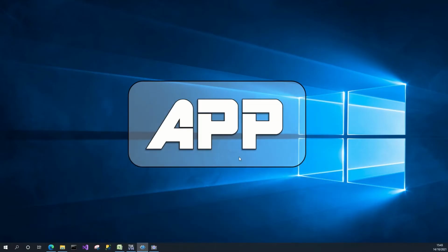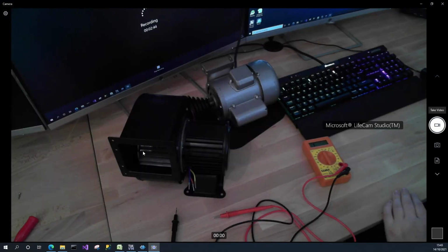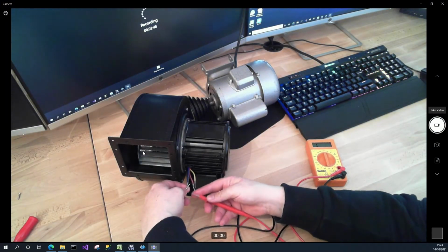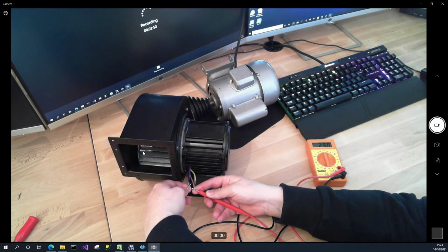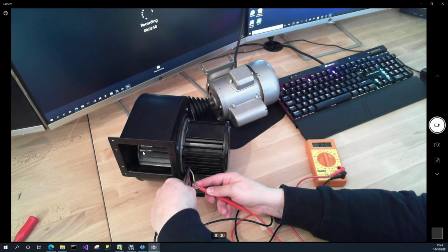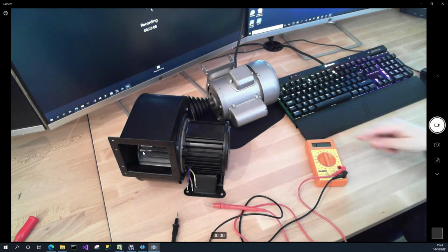So therefore, the rule of thumb is this. Say I have the red to the blue here. If I go back to the camera again, and you can see the multimeter, I have just under 30 ohms. And if I go from the red to the yellow, I have just under 77. It's jumping around a bit, but it'll go between say 75 and 77, okay, on the multimeter.